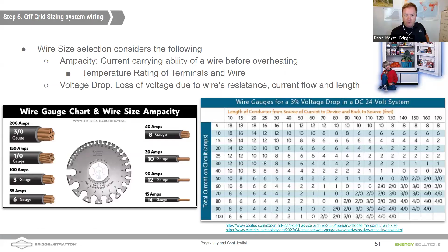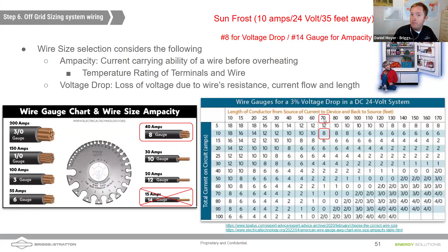If it was an AC fridge, I could run a 15 amp circuit and use 14 gauge wire, no problem. But if we only have 24 volts of pressure pushing that, and it's 35 feet away, I actually need 8 gauge wire, to make sure the wire doesn't have too much resistance restricting the flow. I found that a 3 to 5% voltage drop is usually appropriate - 70 feet round trip, 35 feet there and back, means I need 8 gauge wire. So if you're doing DC architecture, make sure you get out the voltage drop calculator tables or look one up online.